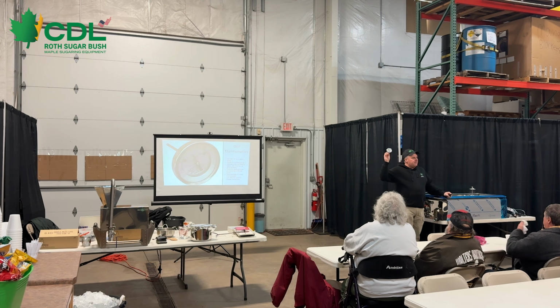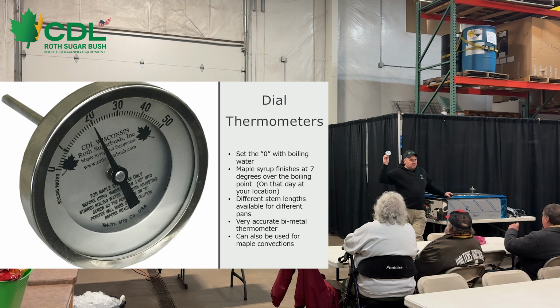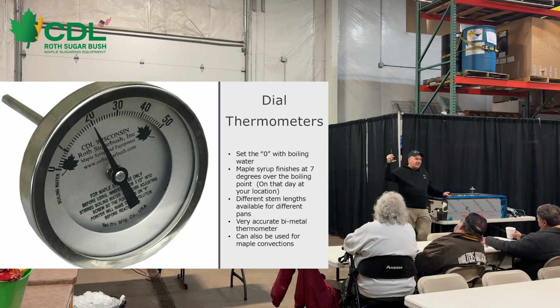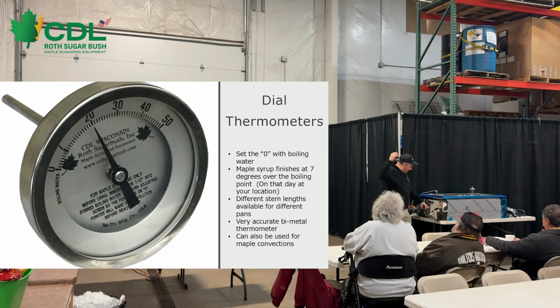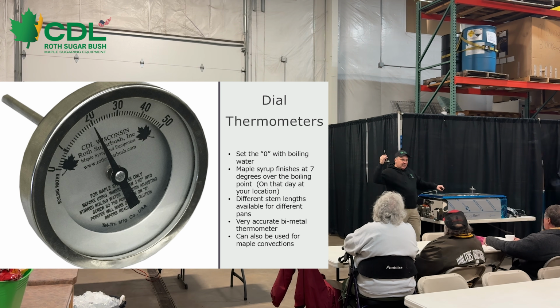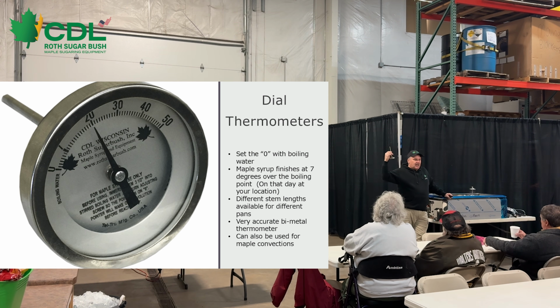Probably the most common on the evaporator is the 0 to 50. When we use the 0 to 50 dial thermometer, we want to make sure that when it's put into the pan, at least half of the stem is submerged in the liquid. Depending on the manufacturer of your pan, we make stem lengths in 3, 6, 9, and 12 inches. So depending on the fitting height on your pan and the angle it's going in, you'll have to select the correct stem size and thread size to thread into your evaporator pan.